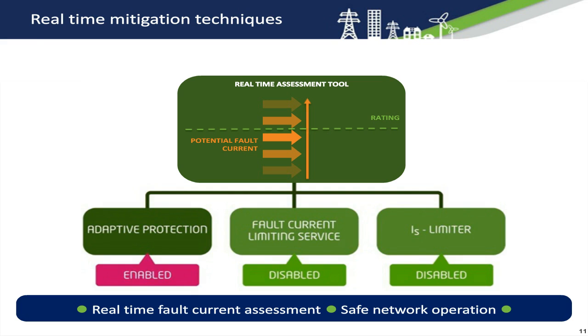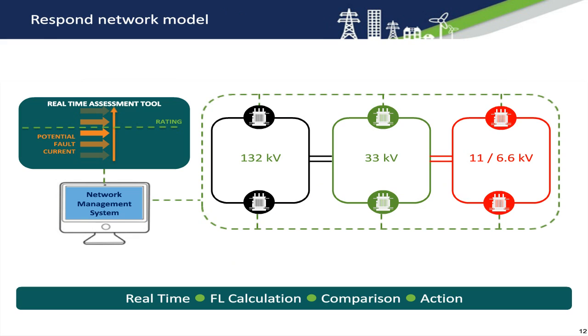For the FLAT tool, fault level assessment tool, to operate correctly, we need an accurate and real-time network model. The network management electrical model is derived from our existing data, including the geospatial, known as GIS, system. And any real-time changes to the network configuration will be presented to the FLAT tool. The tool is designed to calculate fault level after a topology change, or periodically after 5 minutes, allowing near real-time modelling.